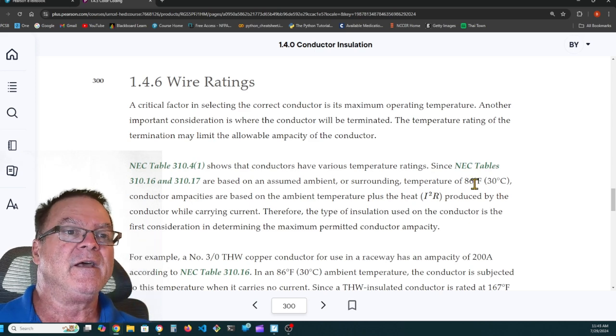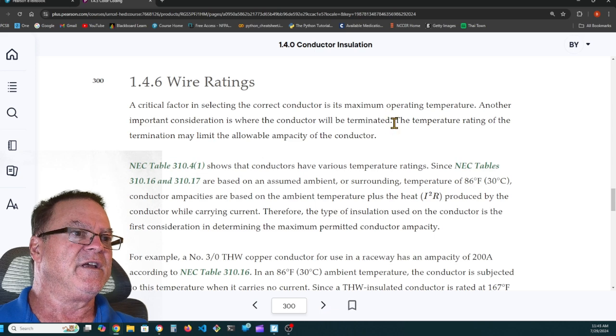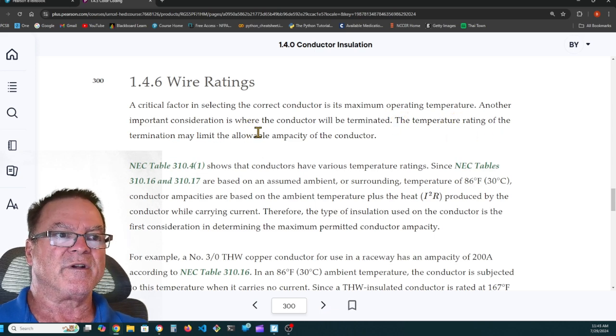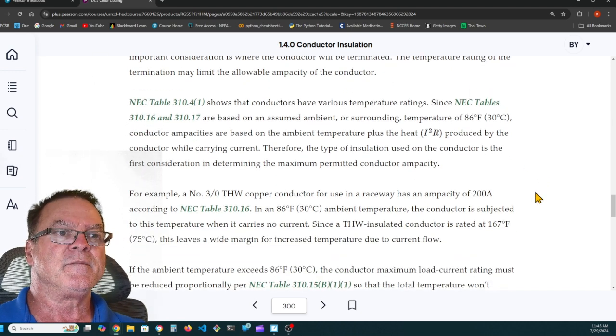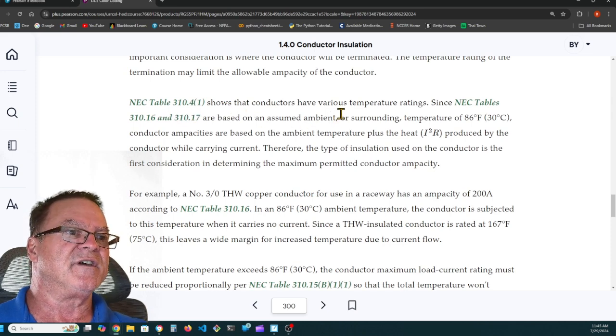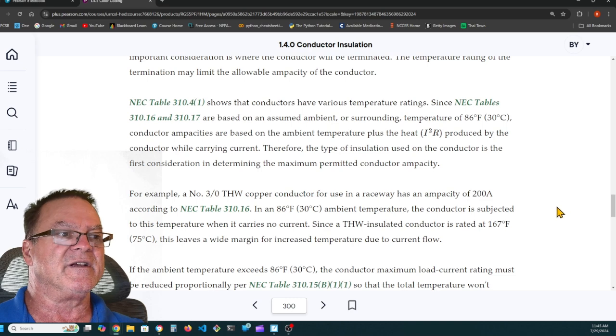1.4.6 wire rating. A critical factor in selecting the correct conductor is its maximum operating temperature. Another important consideration is where the conductor will be terminated. The temperature rating of the termination may limit the allowable ampacity of the conductor. So NEC Table 310.4 shows the conductors have various temperature ratings. Since Tables 310.16 and 310.17 are based on an assumed ambient or surrounding temperature of 30 degrees Celsius, conductor ampacities are based on the ambient temperature plus the heat, the I squared R, produced by the conductor while carrying current. Therefore, the type of insulation used on the conductor is the first consideration in determining the maximum permitted conductor ampacity.